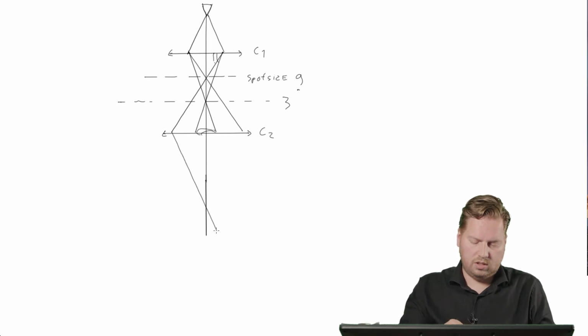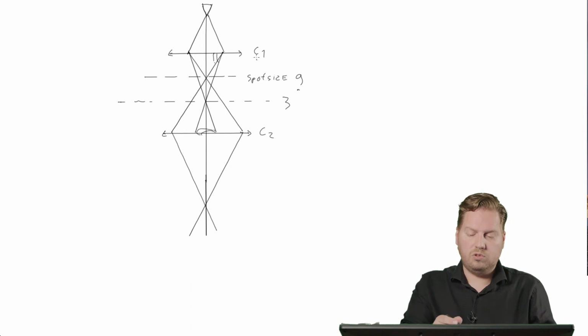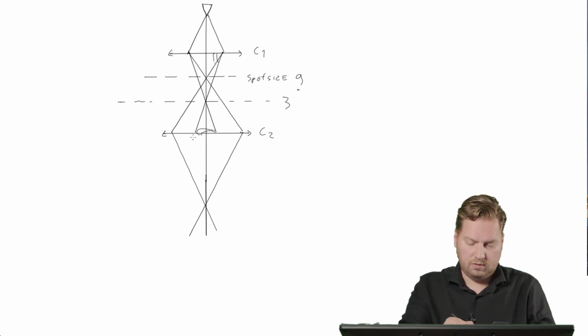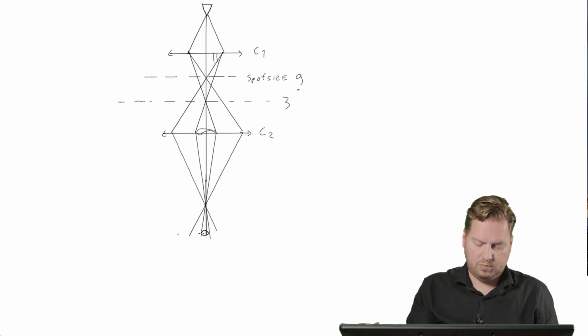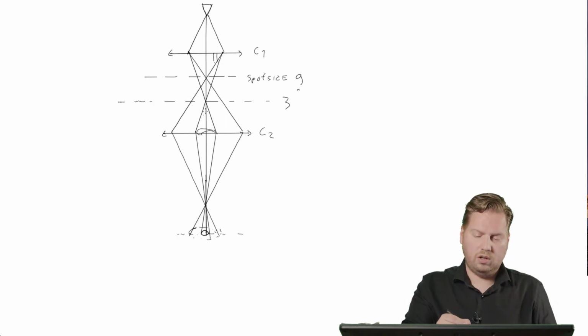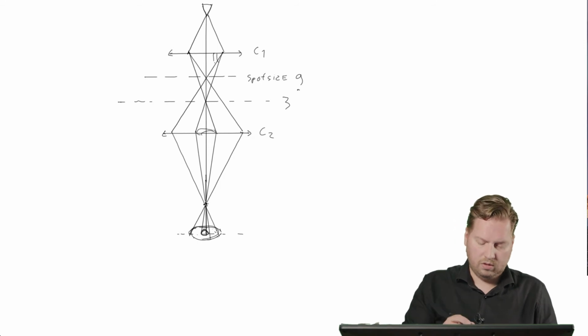So what the C2 lens does is, the C2 lens of course also focuses the beam to a specific spot. But if you change the spot size, your C2 lens adjusts so that the crossover is in the same location. Right, like this. You see here that at the same image plane, you also see that the weaker lens, C1, your smaller spot size, has a smaller spot in your projection after C2 than when you do spot size 9. That is a larger projection because we adjust the C2 lens such that the crossover remains constant if you change the two spot sizes. So here your crossover remains at the same location.